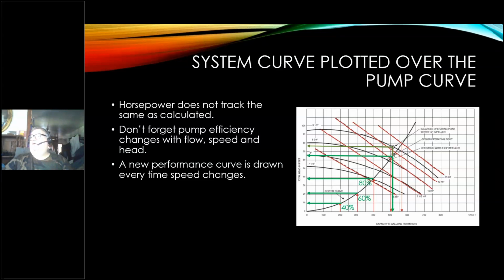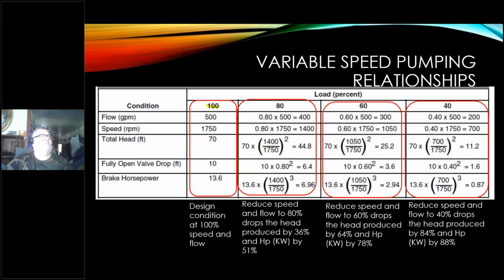So if you look at this chart, as we go down the system curve from 100% down to 80%, 60%, 40%, look at 40%. It's down there at 11 feet at 200 GPM. I don't know if you're going to operate like that at all. You really got to question your operation if you're running down that low for very long periods of time. You're saving a lot of money, but are you actually doing any work? I would think that you would be wasting more money operating way down there at 40% a lot of the time. But that requires a judgment call to change how you're actually operating.